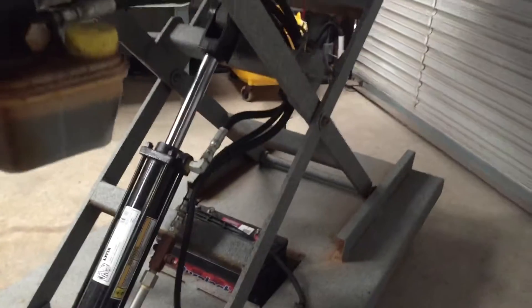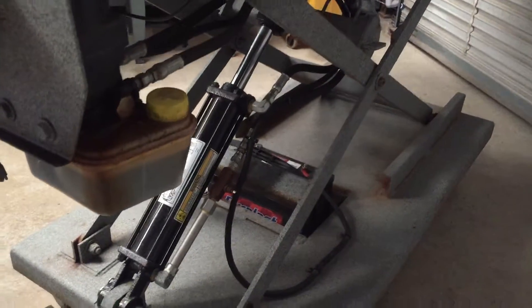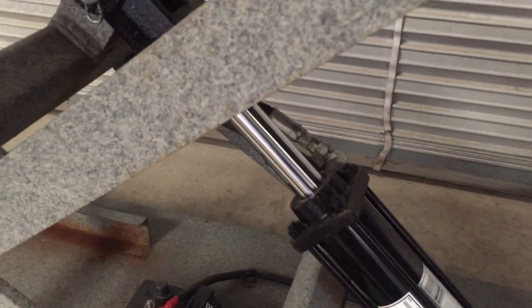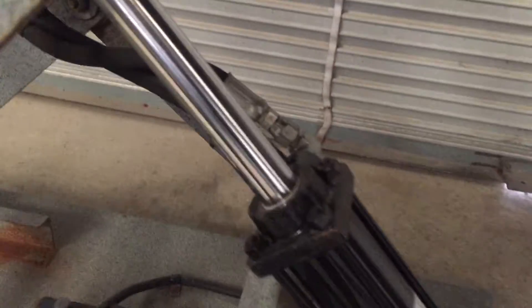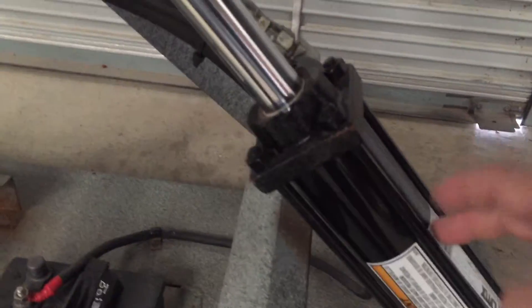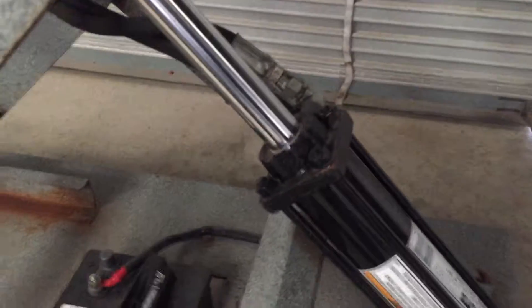No more leaks. Where we had the leak was in the top seal. Let me get the table up. We have the old cylinder here and I'm going to go ahead and replace the seal — I'll make a video of replacing the seal.